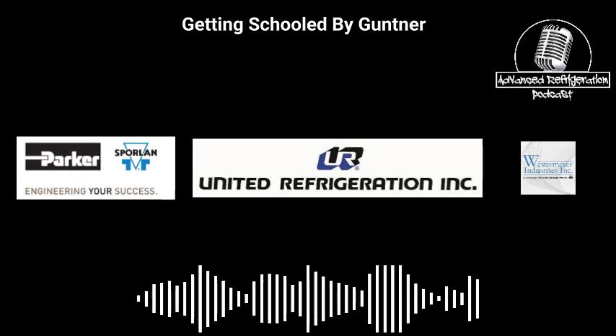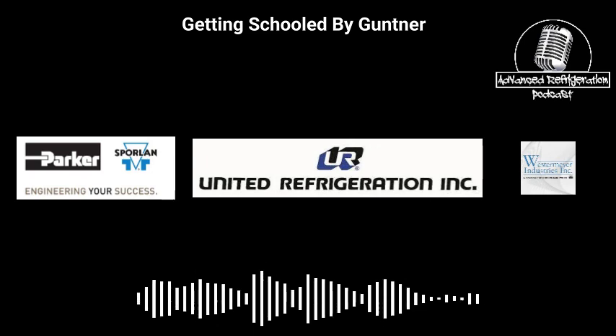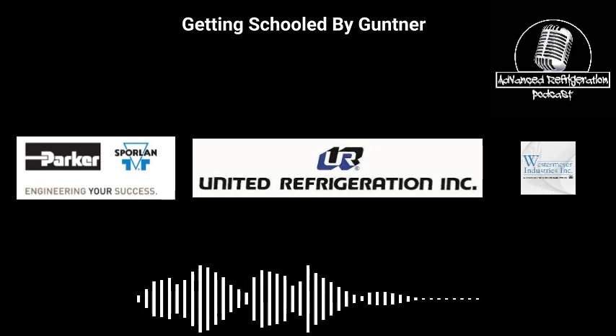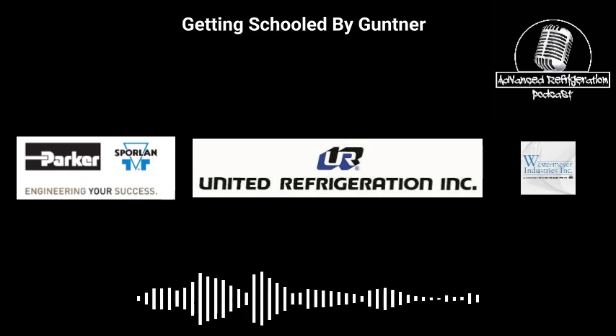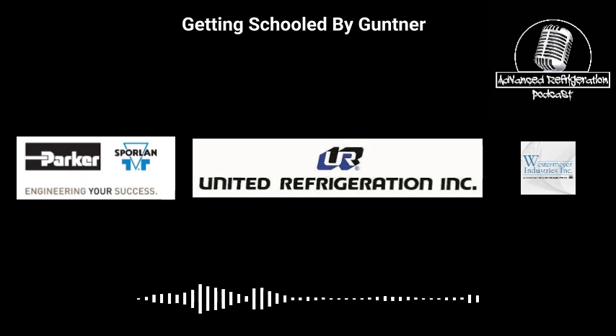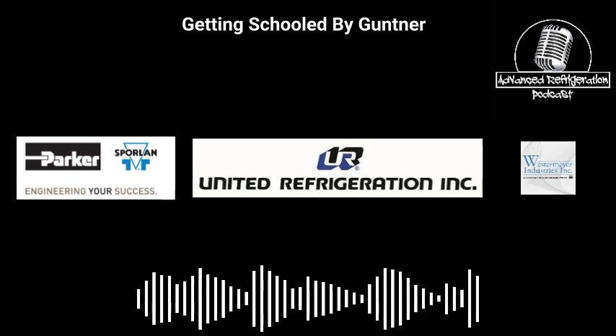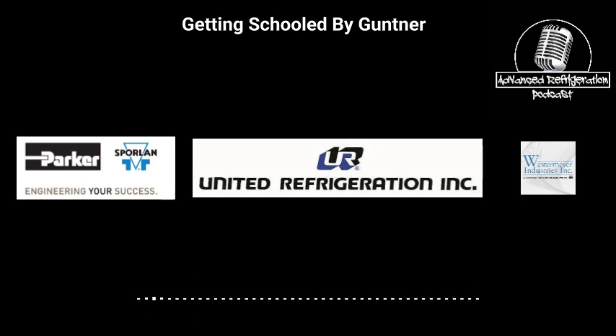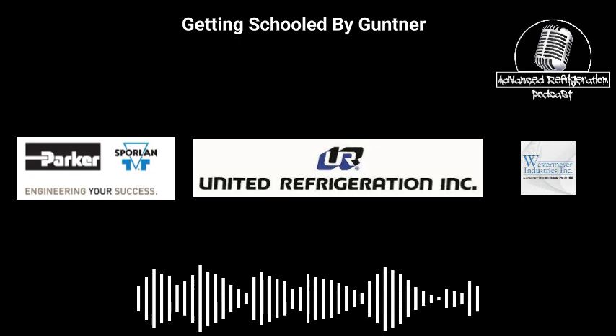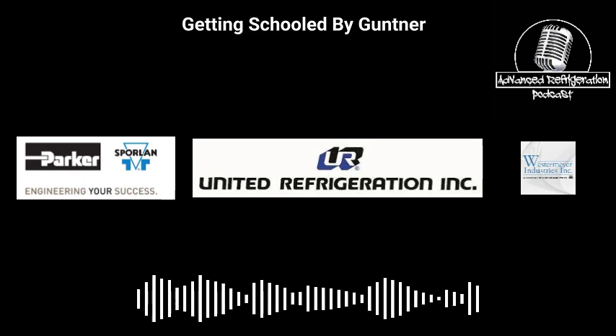And then the third mode is efficiency mode. This is really nice. Not a lot of people use this because you need to have a little bit of information for this. But if you know the cost of water and the cost of energy, and you can put that inside the GHM, our controller will determine which is better to use and operate in that method. So it's actually smart enough to figure out which way is the best way to save energy at that point. Now when it's talking about saving energy, it's just talking about the energy consumption on the gas cooler at that point, correct? Yeah, the energy consumption of the fans. Okay. Yeah, exactly. In here, you can actually see this is a picture of the water meter, the actuator, and the drain valve.